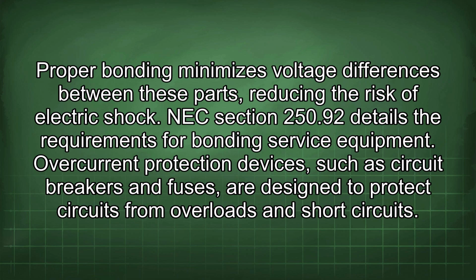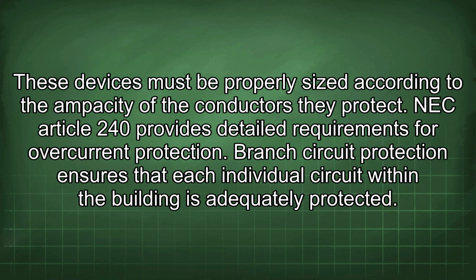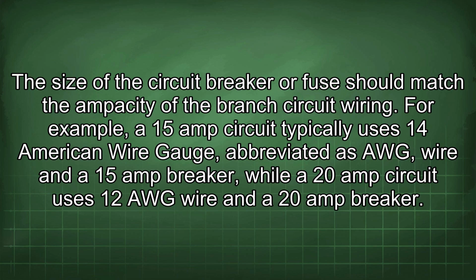Overcurrent protection devices, such as circuit breakers and fuses, are designed to protect circuits from overloads and short circuits. These devices must be properly sized according to the ampacity of the conductors they protect. NEC Article 240 provides detailed requirements for overcurrent protection. Branch circuit protection ensures that each individual circuit within the building is adequately protected. The size of the circuit breaker or fuse should match the ampacity of the branch circuit wiring. For example, a 15 amp circuit typically uses 14 American wire gauge, abbreviated as AWG wire, and a 15 amp breaker, while a 20 amp circuit uses 12 AWG wire and a 20 amp breaker.